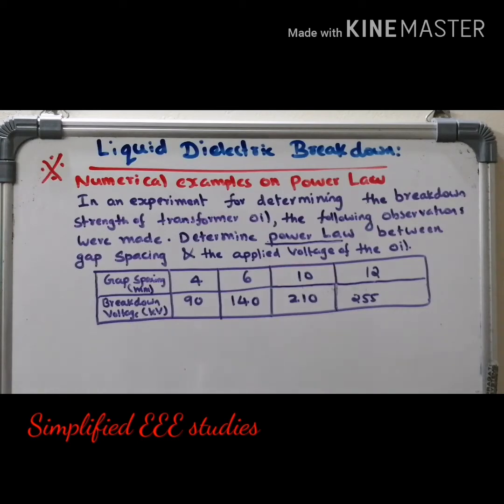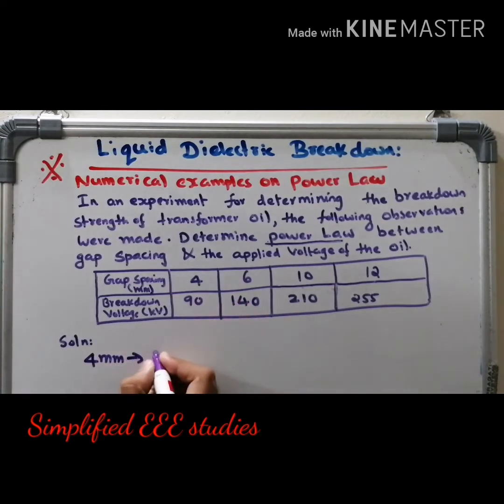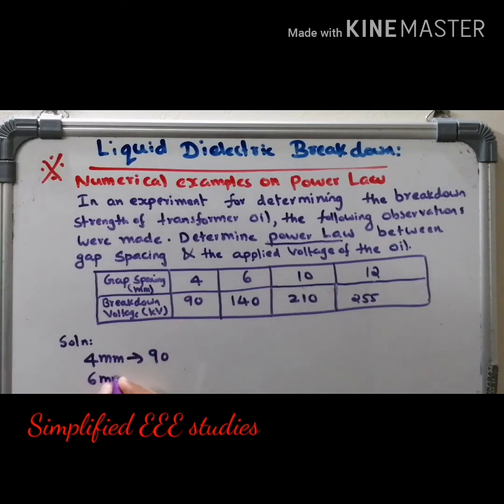This is a transformer oil. They have taken it and applied particular voltage at a particular distance. For example, at the gap spacing of 4 mm, the breakdown voltage is 90 kV. When you maintain the gap distance at 6 mm, the obtained value of the breakdown voltage is 140 kV.